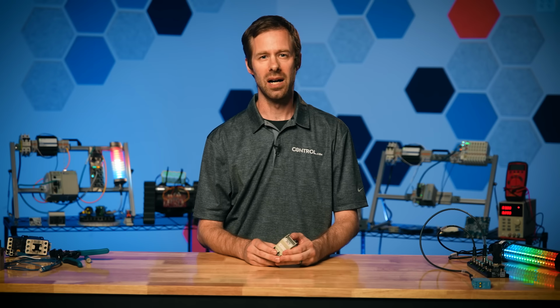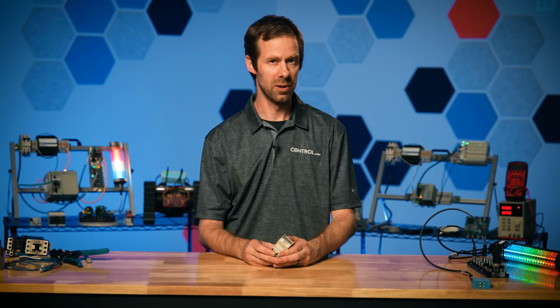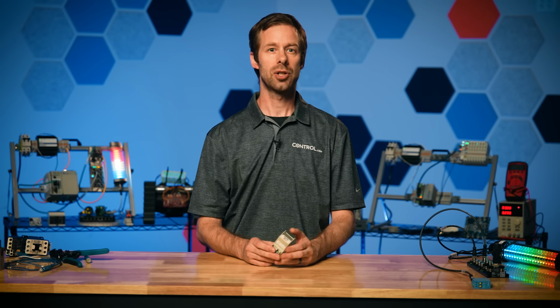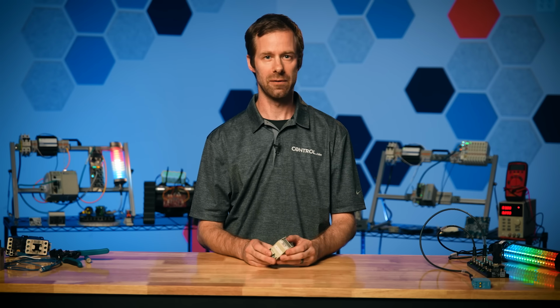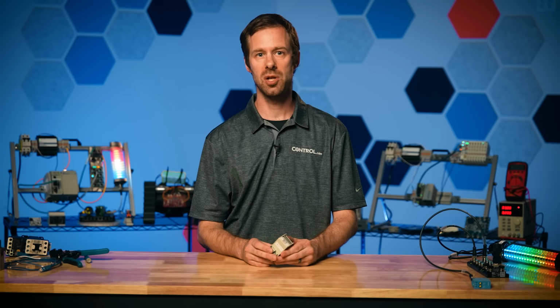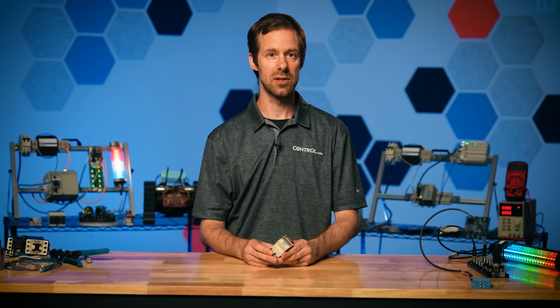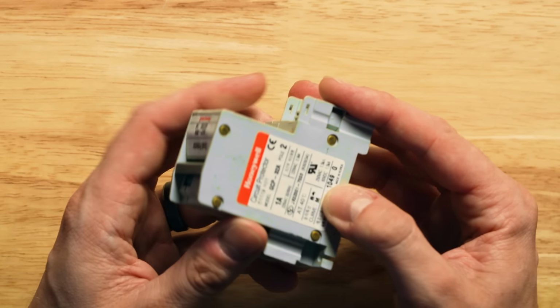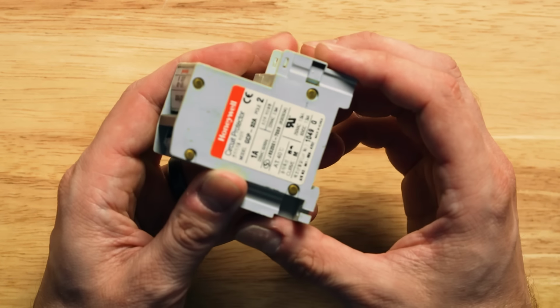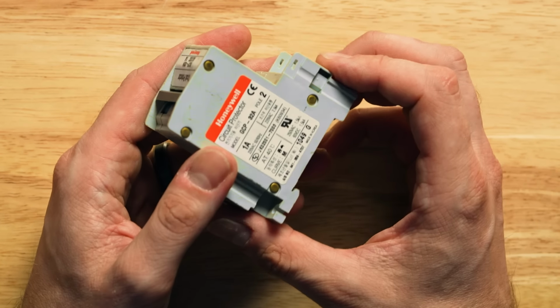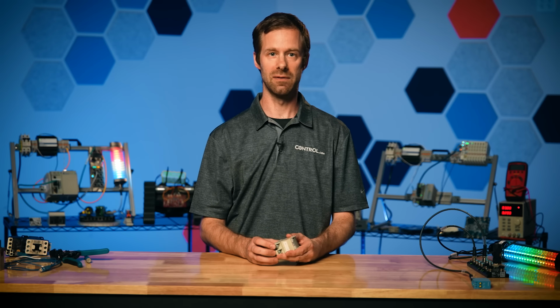Did you know that not all circuit breakers are created equal? Well, we know that the current capacity is the main rating for a circuit breaker. Some of them can be 1 amp, 2 amp. Maybe in your house there's 15, 20 amp circuit breakers. But there's something even more important in industrial devices that often gets overlooked, and it's the purpose of the circuit breaker. The curve, which is a rating on the circuit breaker, tells how quickly it will trip under certain operating conditions. In industry, we have a lot more inductive devices.